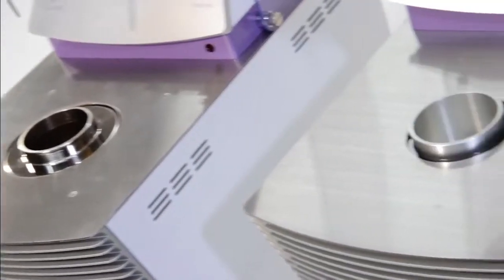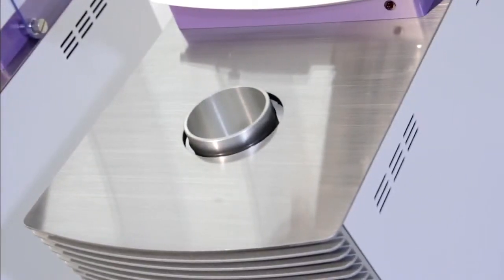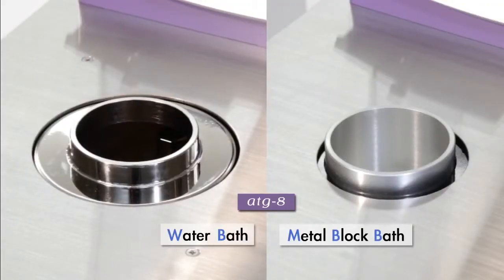For the TAG closed cup, besides the conventional water bath, a metal bath type with Peltier cooler system is available for lower temperature testing.